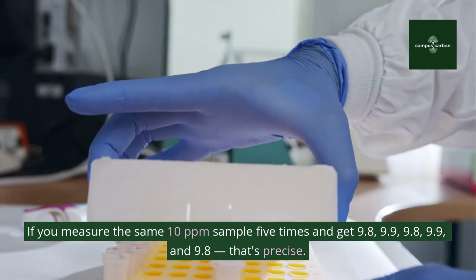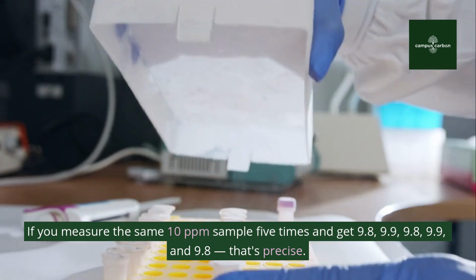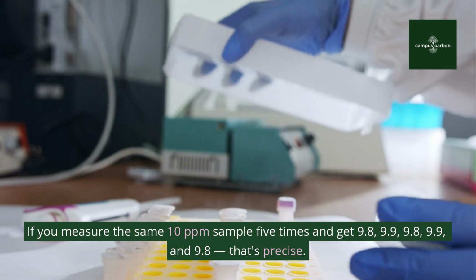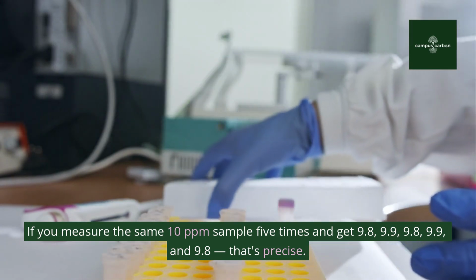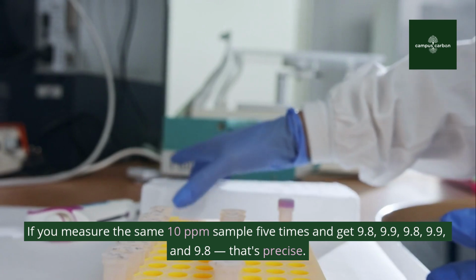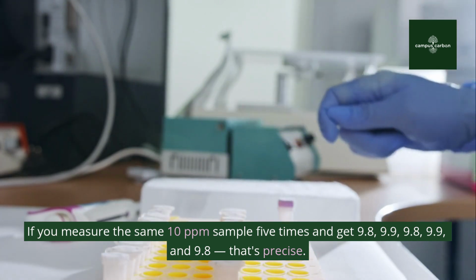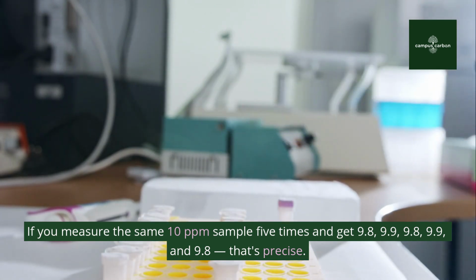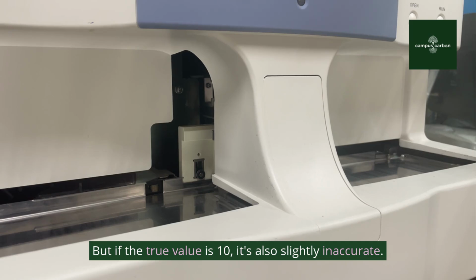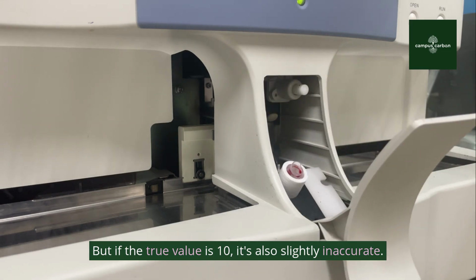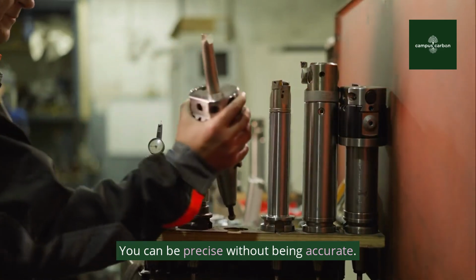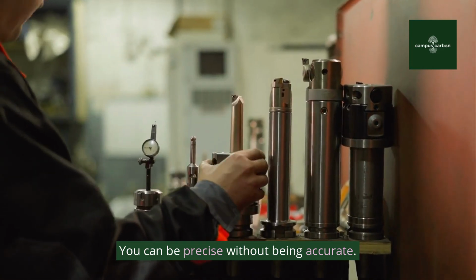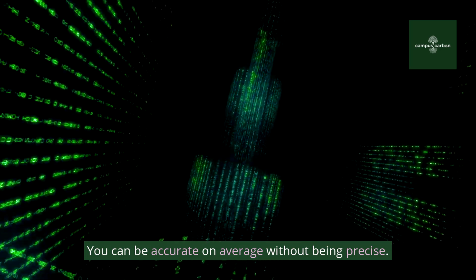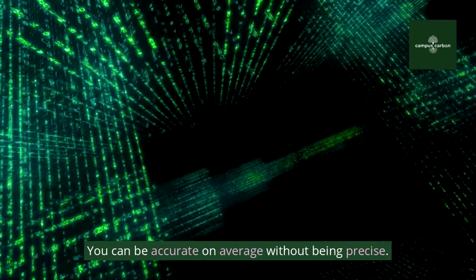If you measure the same 10 ppm sample 5 times and get 9.8, 9.9, 9.8, 9.9, and 9.8, that's precise. But if the true value is 10, it's also slightly inaccurate. You can be precise without being accurate. You can be accurate on average without being precise.